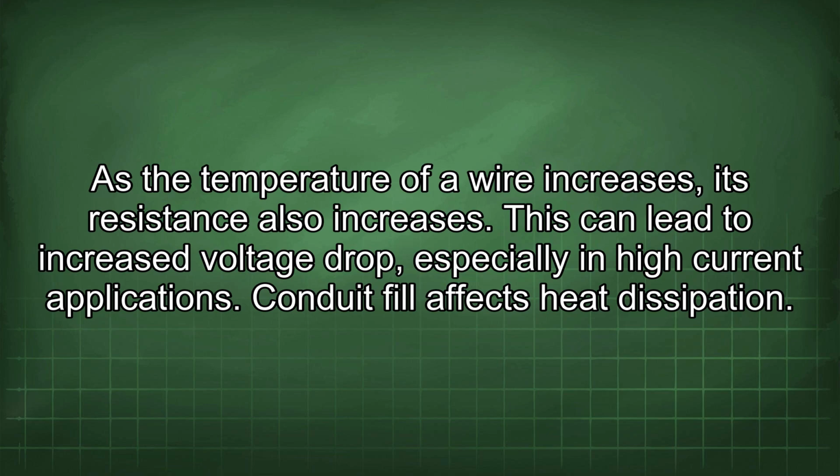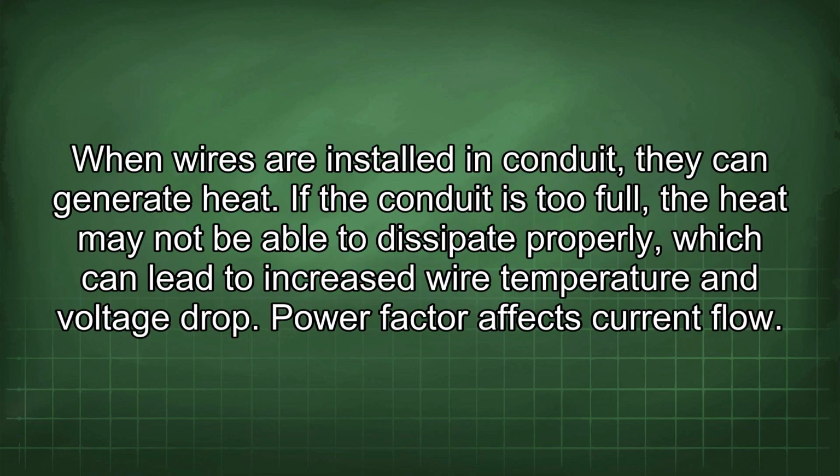Conduit fill affects heat dissipation. When wires are installed in conduit, they can generate heat. If the conduit is too full, the heat may not be able to dissipate properly, which can lead to increased wire temperature and voltage drop.